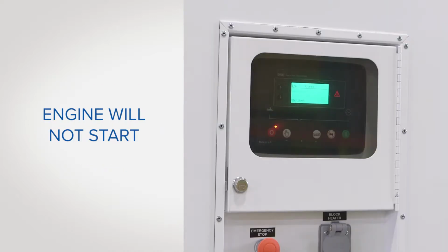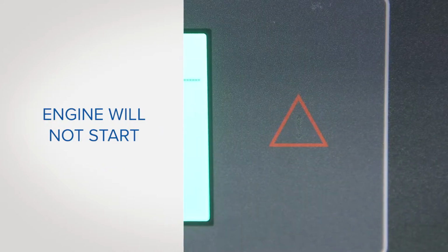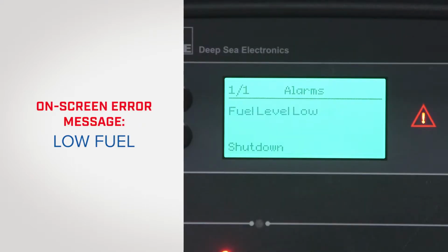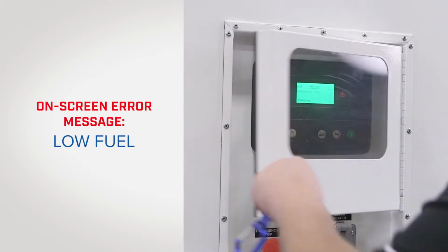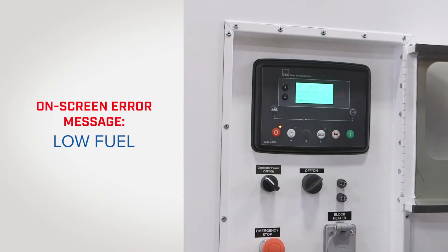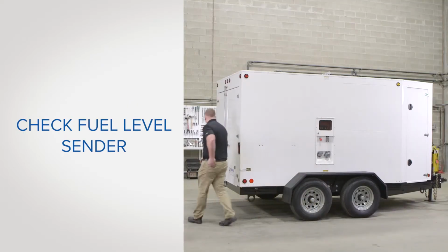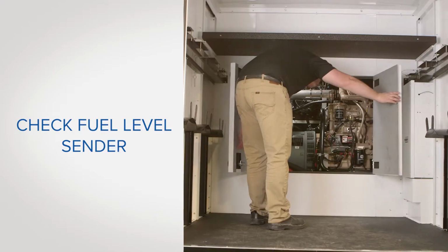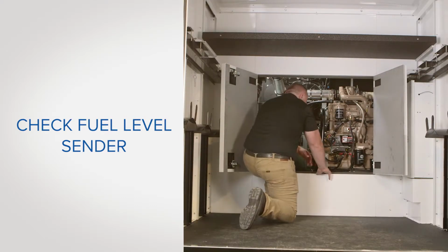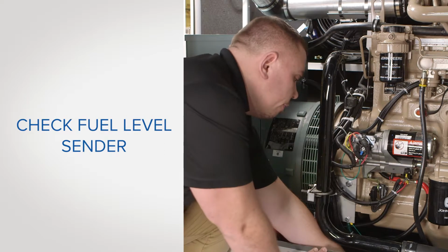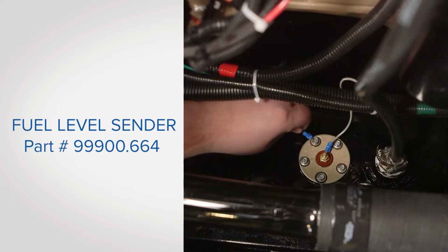There are several steps you can take if your engine will not start. You may see a low fuel level warning on the control panel screen. If you know the unit has fuel, you may have a bad fuel level sender or a bad ground connection on the fuel level sender. First, check the ground connection. If that does not resolve the problem, you will need to replace the fuel level sender.